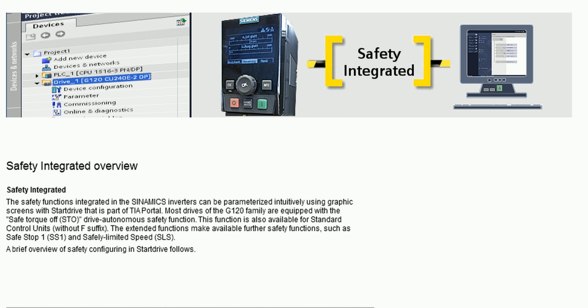Safety Integrated. The safety functions integrated in the SINAMICS inverters can be parameterized intuitively using graphic screens with Startdrive, which is part of TIA Portal. Most drives of the G120 family are equipped with the Safe Torque Off (STO) drive-autonomous safety function. This function is also available for standard control units, without F suffix. The extended functions make available further safety functions, such as Safe Stop 1, SS1, and Safely Limited Speed, SLS.